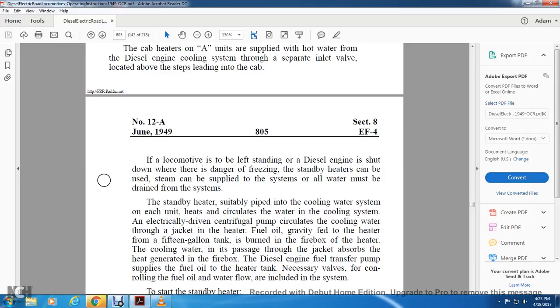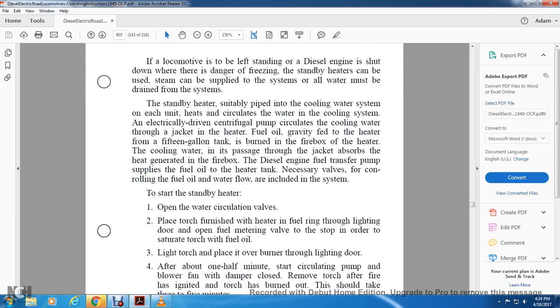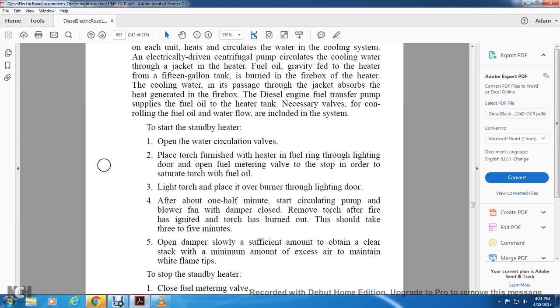Fuel from a 15 gallon gravity heater tank is burned in the firebox to heat the cooling water. The water passing through the jacket absorbs the heat generated in the firebox. The diesel engine fuel transfer pump supplies the fuel oil heater tank, with the necessary valve for controlling the fuel oil flow included with the system. To start the standby heater, open the water circulation valve, place the torch furnished with the heater in the fuel ring, and through the lighting door, open the fuel meter valve to saturate the torch with fuel oil. Light the torch, place it over the burner through the lighting door. After about one-half minute, start the circulating pump and blower fan with the damper closed, but remove the torch after the fire is ignited and the torch has burned out.